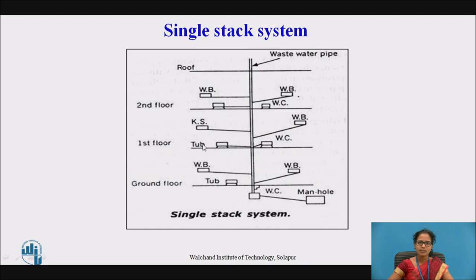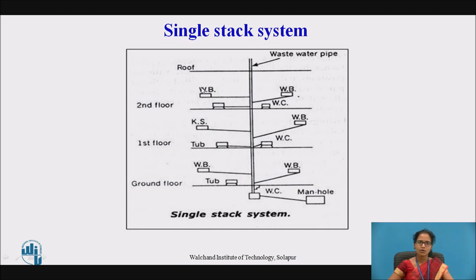The wash basins, WCs, kitchen sinks, and tubs — with their traps — are all connected to this vertical pipe. All the sanitary waste is collected in this single vertical pipe and directly connected to the drainage system. This system is economical as it consists of only one single pipe, and the cost is less. It is effective if the depth of the water seal is more than 75 mm. No separate pipe is provided for ventilation. That is why it is called the single stack system.